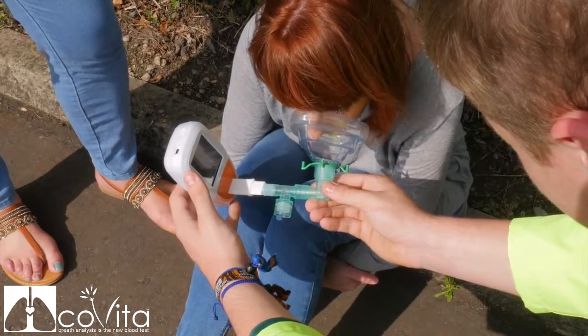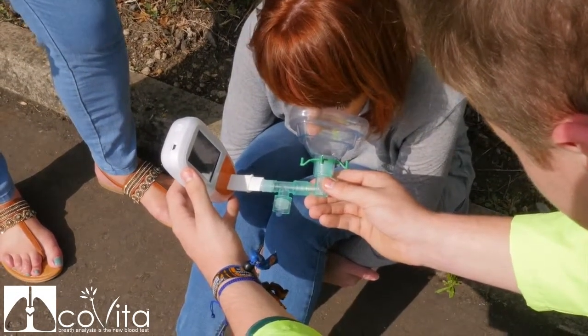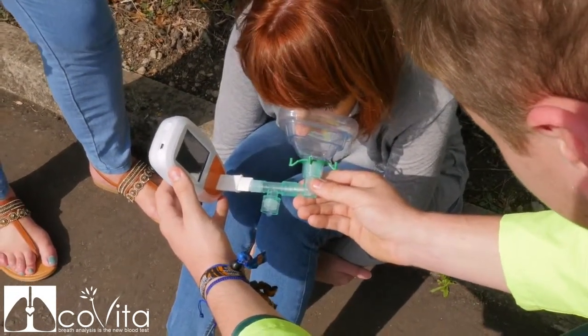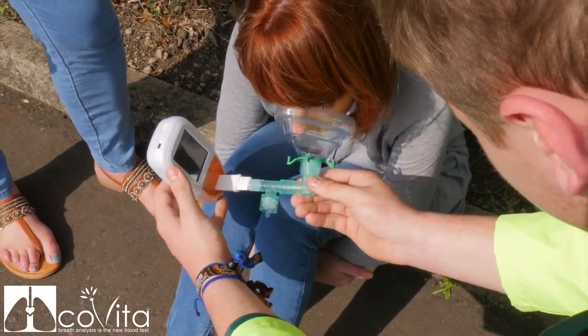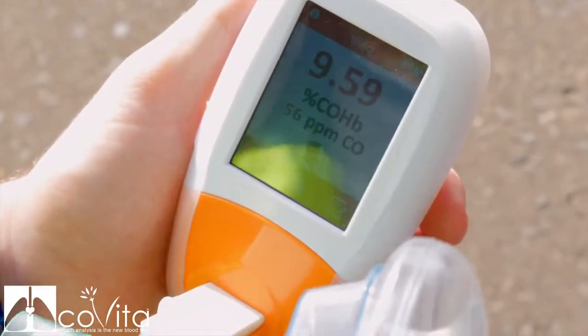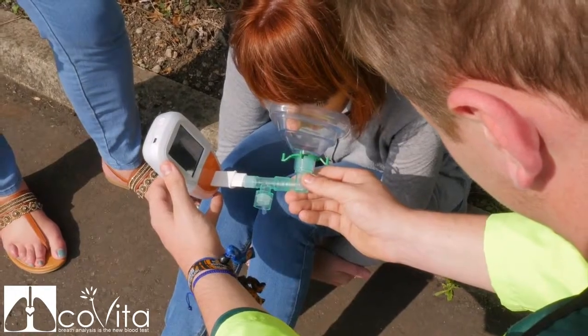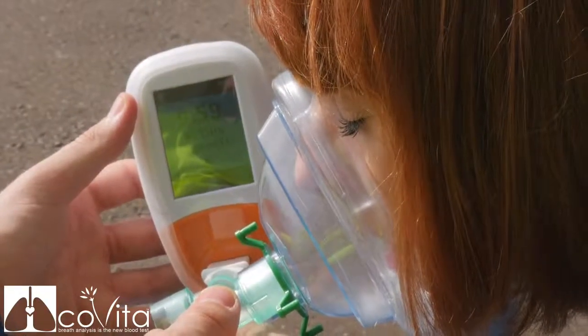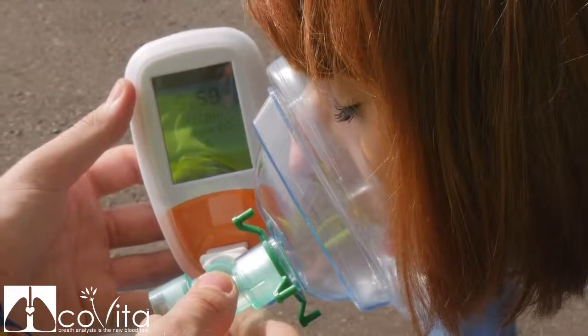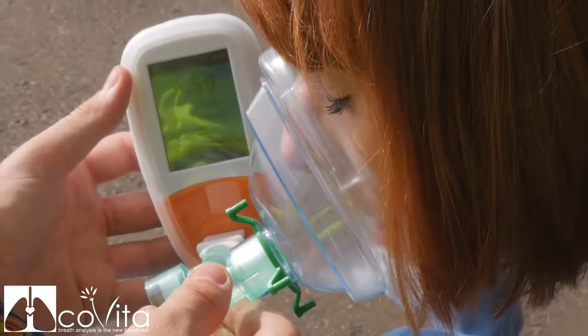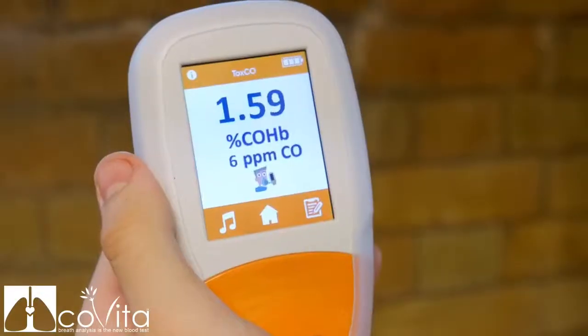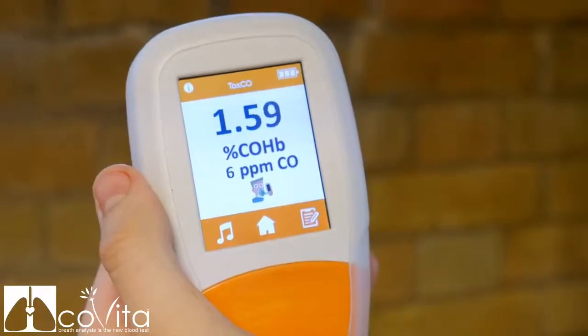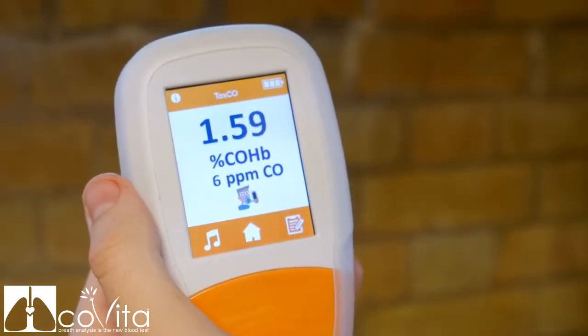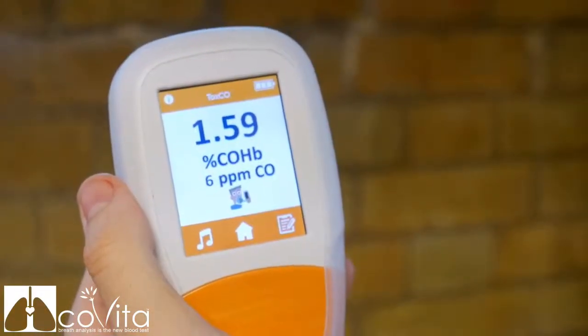Breathe normally into the face mask and the reading will rise and stabilize on screen, and you can mute the monitor if necessary. If the patient is unconscious, make sure the face mask is secure and the ToxCO will sample their breathing. When the test is finished, you can either save the reading or return to the home screen. The ToxCO can save up to 500 breath test readings.